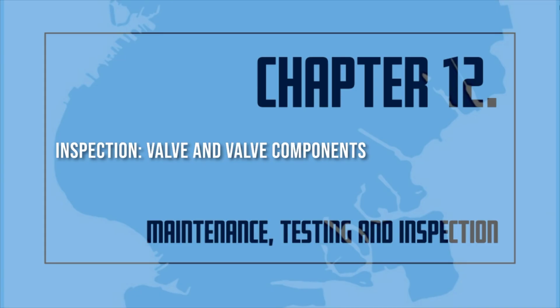Dry pipe valves/quick opening devices. The valve enclosure heating equipment, if subject to freezing, shall be inspected daily during cold weather for its ability to maintain a minimum temperature of at least 40 degrees Fahrenheit. Valve enclosures equipped with low temperature alarms shall be inspected weekly during cold weather. Exterior dry pipe valves shall be inspected monthly to ensure they are free from physical damage, the intermediate chamber is not leaking, all trim valves are in the appropriate open or closed position, and electrical components are in service.